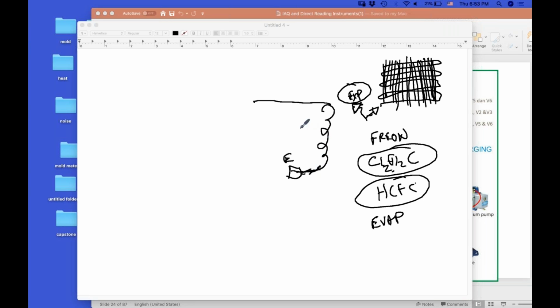So that freon, if we put a fan in here, what happens is there's a little fan in there, it's running continuously. We can pull air in from the room and blow it out through that coil and cool the air. That freon is so cold that not only does it cool the air, but it also cools it so much that it condenses the moisture out of the air. So we have a little condensate pan on the bottom of that with a little tube that comes off and might go out the window. In the old days, when you walked underneath one of these units, you'd feel the water dripping on your head. I'll explain to you in a couple of minutes why that doesn't happen anymore.